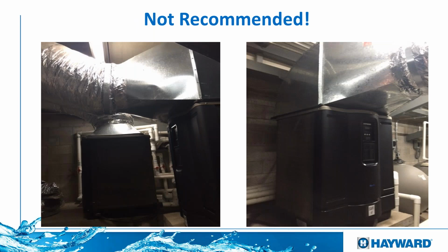You can see this small example of what happened here. This customer made an installation indoors, and they had to create some kind of ducts so they can get that cold air outside of that room without making that room a freezer. Okay, because that will happen if you don't have that kind of duct. That little room will become like a refrigerator after a little bit, because again, the heat pump will be sucking all the heat out of the surroundings, and it gets to a point where there's no more heat to transport because everything becomes cold. So again, this is not something we recommend. Definitely to be outside.